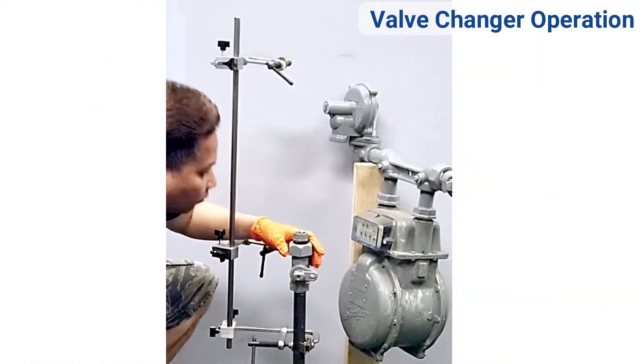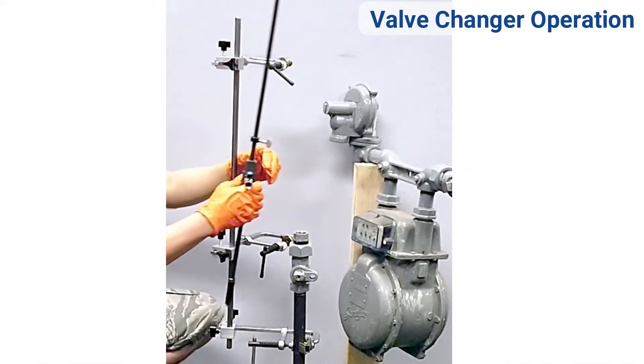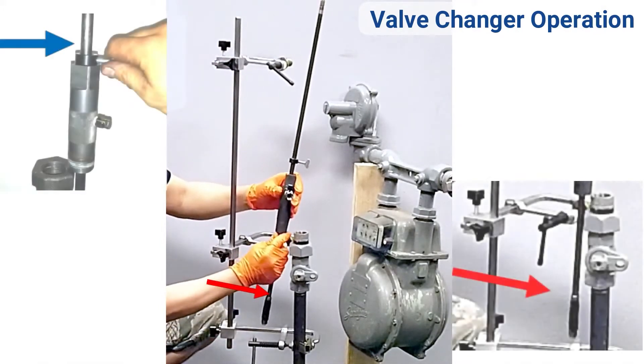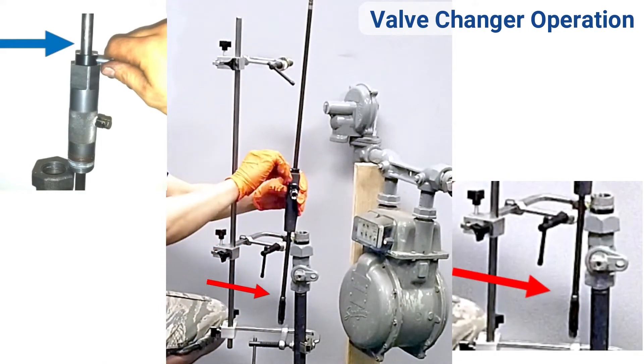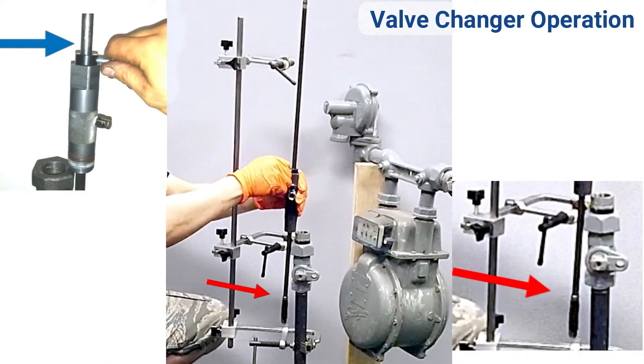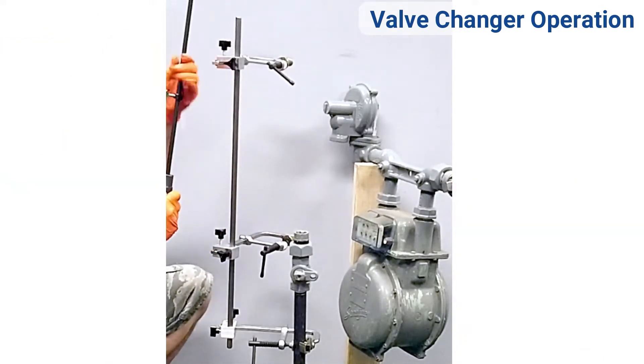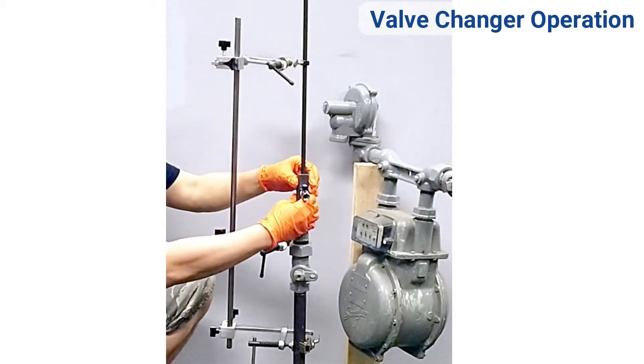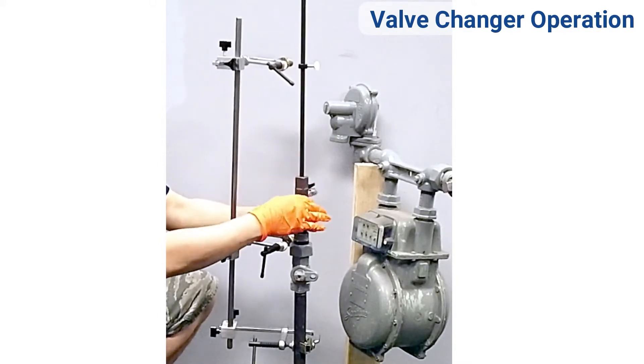Measure the desired depth of the rubber stopper. Place the threaded section of the stuffing box on top of the lip edge of the meter valve. Push down on the shaft to achieve the desired depth by lining up the metallic edge of the rubber stopper to at least below the meter valve. Slide the depth collar to the top of the stuffing box and tighten the thumb screw.